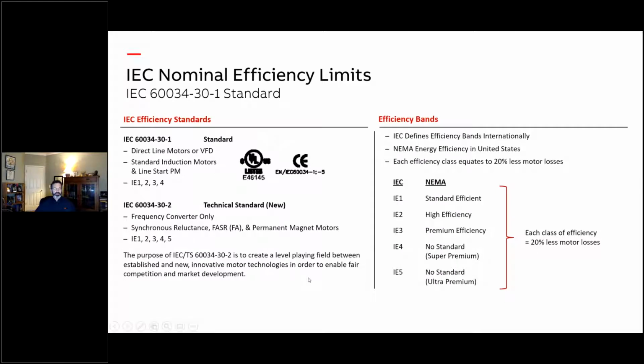These are the IEC standards. Again, there's standard efficient, high efficient, and premium efficient. In the NEMA world, there's really no standard above here, although people have been calling it super premium or ultra premium. That's why we tend to use these IEC standards, because they do actually define it. But it's not really that complicated. Each class of efficiency has 20% less motor losses, and that's how you get up to higher efficiency.